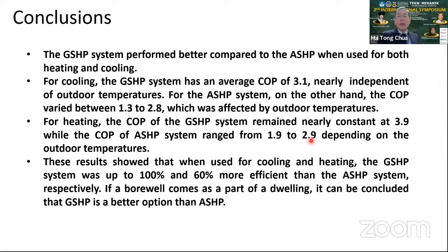Again, you can see here, this 2.9, why is it needed? Again, this 2.9 is when the outdoor air is pretty warm, when we do not need heating. That's only when it comes closer to the ground source heat pump. But typically it is a lot lower, as low as 1.9 versus 3.9. So overall, on the whole, and not going to the extreme, it can be 60% more efficient than an ASHP system. I hope that answers your question. Okay, thank you, Prof. You're welcome.